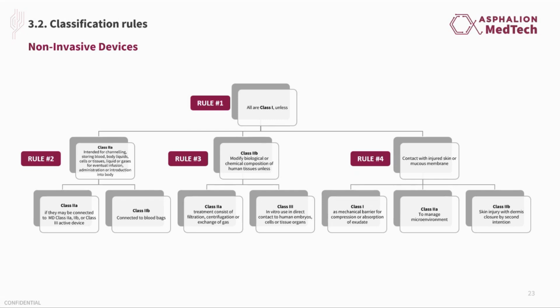Remember that the guidance document MDCG 2021-24, guidance on classification of medical devices, can also assist in the classification process, giving more definitions, examples, and so on. Okay, so rules 1 to 4 are applicable to non-invasive devices. Rule 1 defines devices as class 1 unless rules 2 to 4 apply. And then we have rules 2, 3, and 4. For example, rule 4 is for non-invasive devices in contact with injured skin or mucous membrane, right?